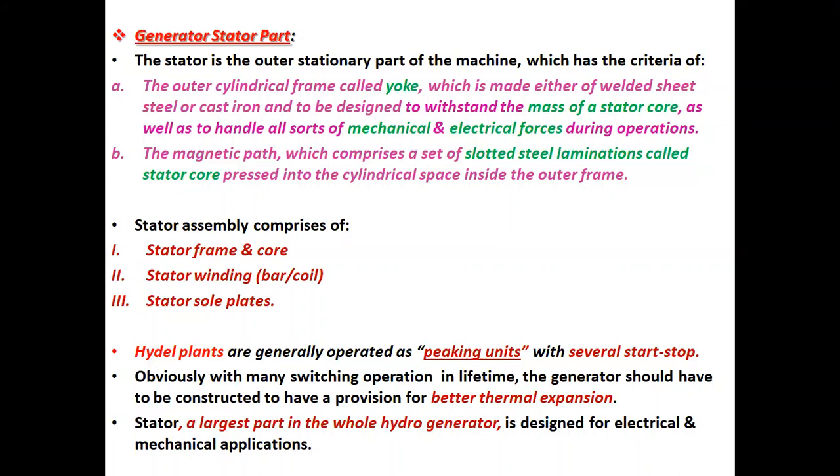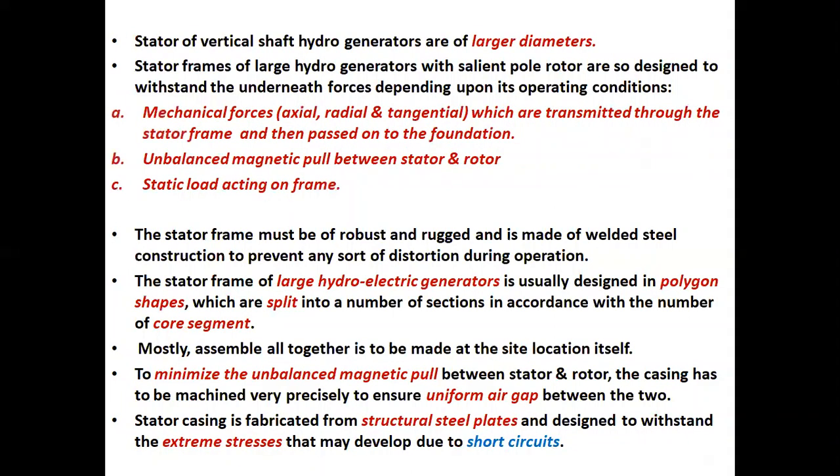Hydro plants are generally operated as peaking units with several start-stop cycles. Obviously, with many switching operations in their lifetime, the generator should be constructed to have a provision for better thermal expansion. The stator, the largest part in the whole hydrogenerator, is designed for electrical and mechanical applications. Stator of vertical shaft hydrogenerators are of larger diameters. Stator frames of large hydrogenerators with salient pole rotor are designed to withstand the underneath forces, depending upon its operating conditions.